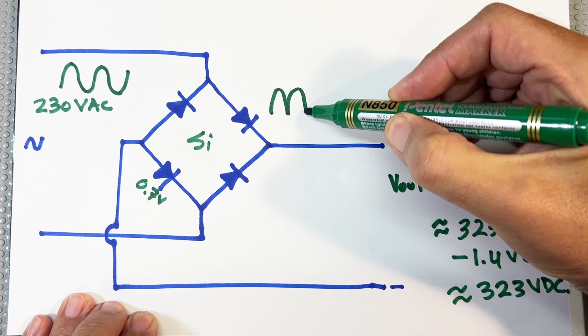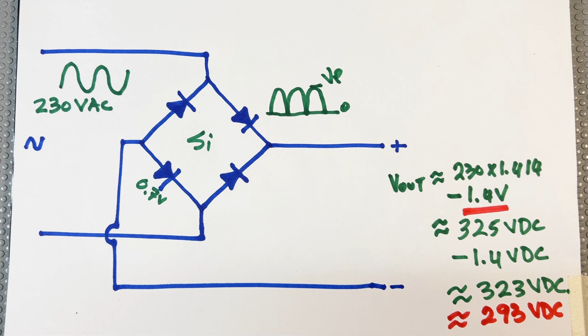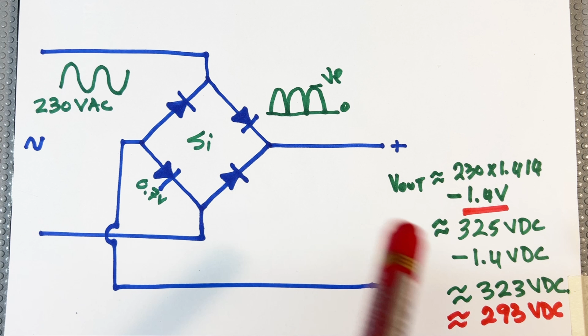What happens with a selenium rectifier is slightly different. You've still got 4 diodes, but the drop isn't 1.4 volts - it can be like 20, 25, or 15 volts depending on voltage and current, much higher. So with a selenium rectifier you might see not 323 volts but something like 293 - a drop of about 30 volts. That's not unreasonable, and the problem is this drop gets higher as the selenium rectifier ages, because it creates a lot of heat inside, deteriorating the components and making the drop bigger.